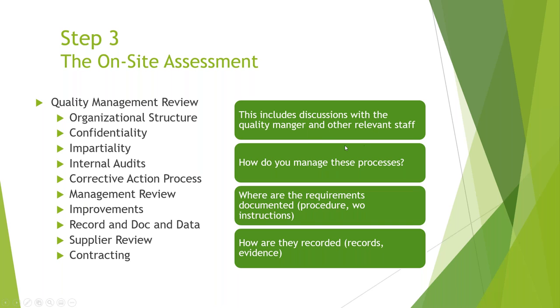This usually includes discussions with the quality manager and any other relevant staff. We want to know how you manage these processes and where the requirements are documented. For example, if you have a procedure on how you handle internal audits — with a plan, doing them quarterly or annually — we want to see the procedures, work instructions, and whatever you have in place. It's not only important to see a procedure, but we want to see how you've done it. We can look at your procedure and plan, but we want evidence that you did it — like a completed checklist or non-conformances from your internal audit.